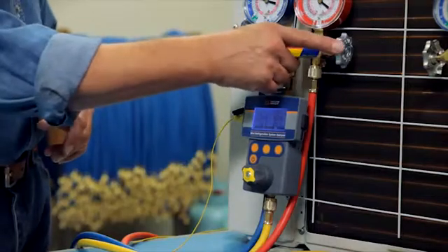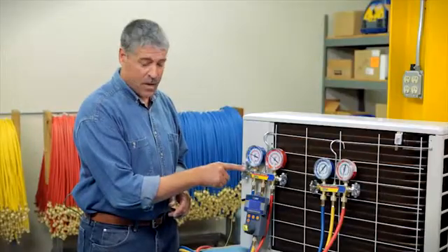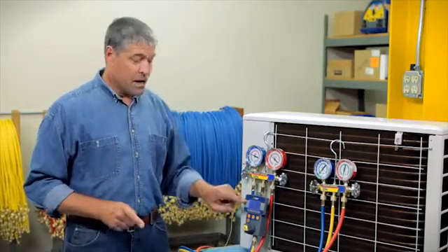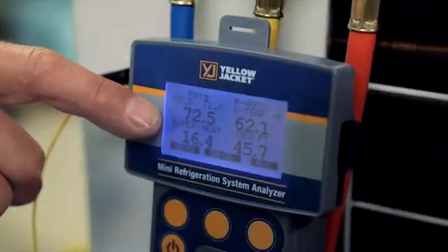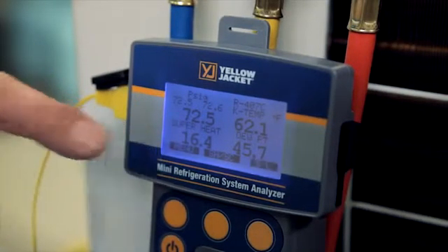To measure superheat, close the high side valve, open the low side valve, and connect the thermocouple bead to the suction line of the system. The readout screen will then display the low side pressure and temperature readings from your thermocouple probe, as well as the dew point and calculated superheat values.